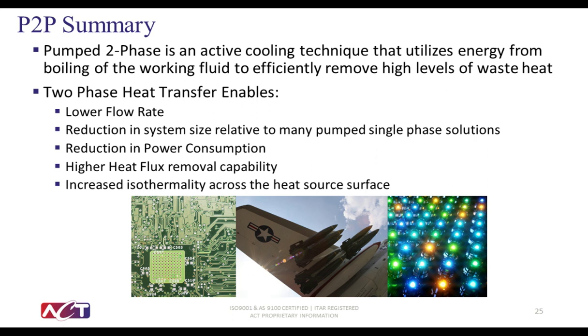In summary, pump two-phase is an active cooling technique that utilizes energy from the boiling of the working fluid to efficiently remove high levels of waste heat. Two-phase heat transfer enables lower flow rate, reduction in system size relative to many pump single-phase solutions, reduction in power consumption, higher heat flux removal capability, and increased isothermality across the heat source surface.